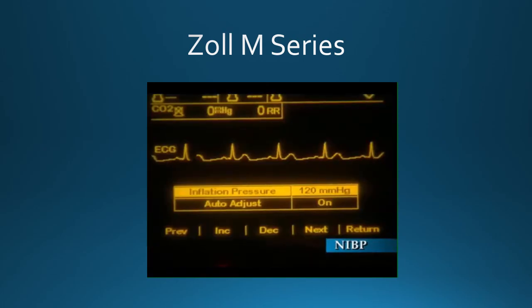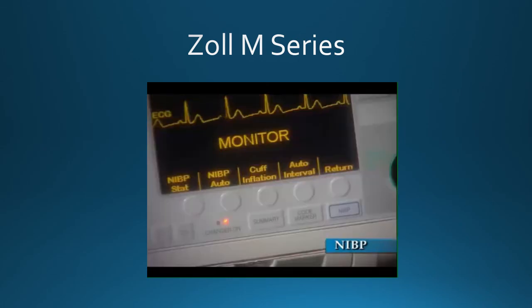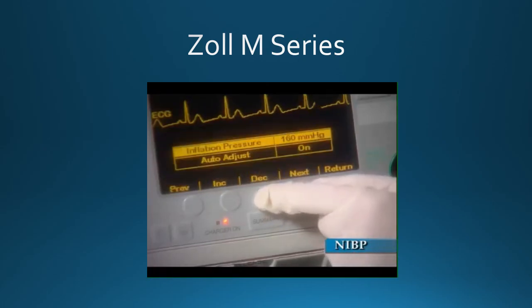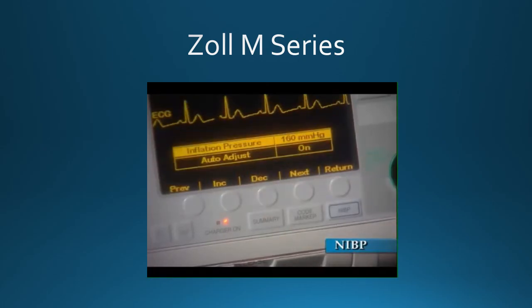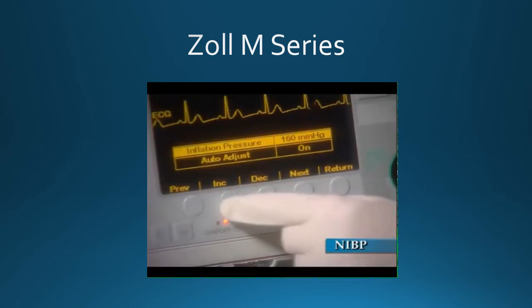Before taking a measurement, check that the initial cuff inflation pressure is appropriate for the patient. The default cuff inflation pressure is 160 millimeters of mercury. To adjust the inflation pressure, press the Cuff Inflation soft key and then press the Increase or Decrease keys.